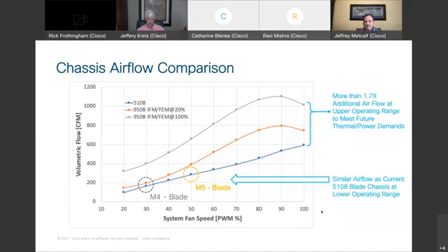Okay. On the bottom, you have a blue line that represents the airflow as you're increasing the system fan. So you basically see, at the lowest operating point around 20%, the system's delivering about 160 CFM. And if the fans are all running at 100%, you're delivering just around 600 CFM. Okay. And I show some intercepts on that line, an M4 and M5 blade, the typical operating points. So the fans are operating around 30% or 50% fan speed when those blade versions are installed.